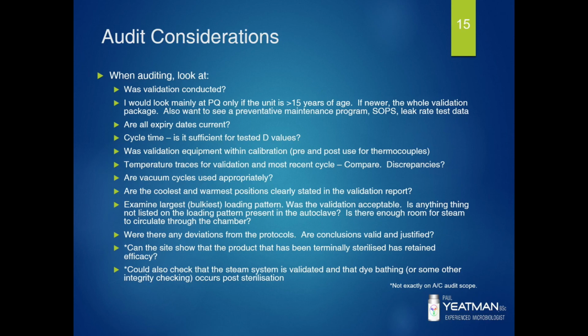You could also check that the steam system is validated and that dye bathing or some other integrity checking occurs post-sterilisation. So again, you've gone to the trouble of filling your product and terminally sterilising it. You can't then immediately release the product because that sterilisation action might have compromised the vials or ampoules by producing cracks in them. So you dye bath it or do some other sort of integrity checking. With the dye bath, once the items have been tested, they'd all be visually examined, and if any had dye in them, then they get thrown out, and the rest of the samples should be integral, which then means that they could be released for use.